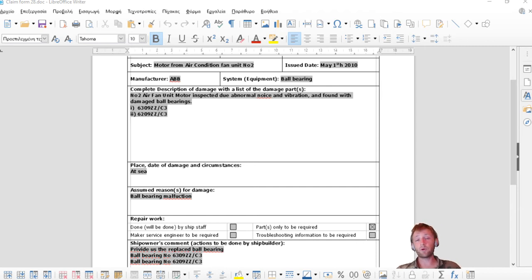So they become more experienced and can eliminate bigger problems that can occur from a breakage of the motor, a total breakdown of the winding or the stator itself—mostly the winding, because that is the area most affected in case of damage to the ball bearings or the cases that hold them.